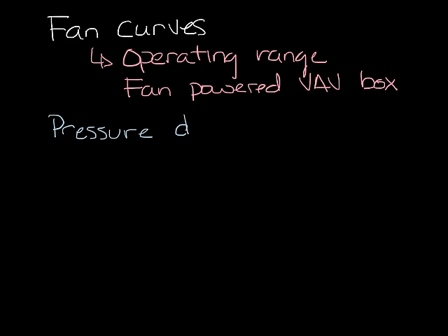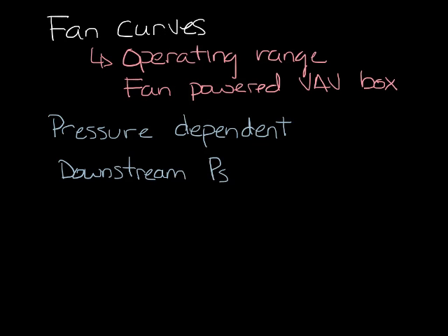Fans are pressure dependent. This means that their performance depends on what pressures they operate against, called the downstream static pressure. In other words, the airflow, the CFM, is dependent on the static pressure that they're working against. In general, the higher the pressure, the lower the CFM.